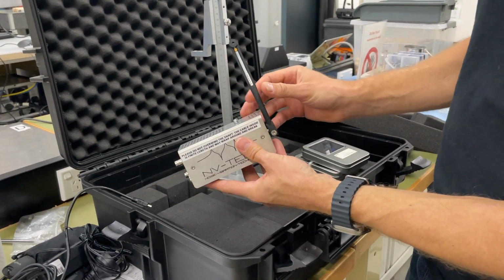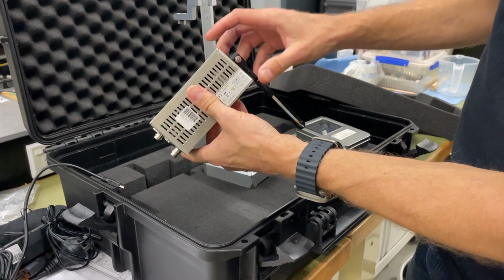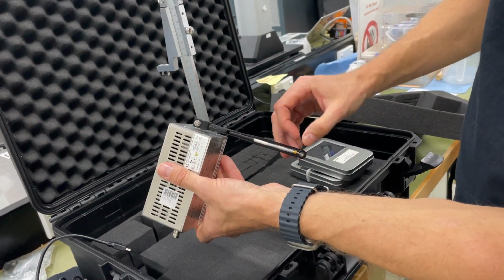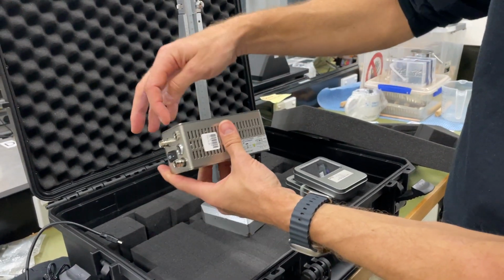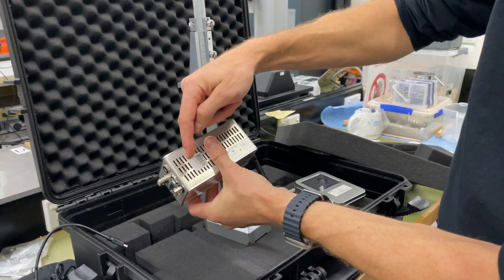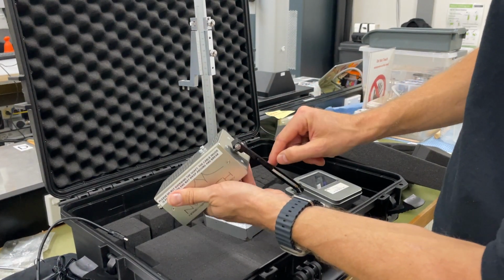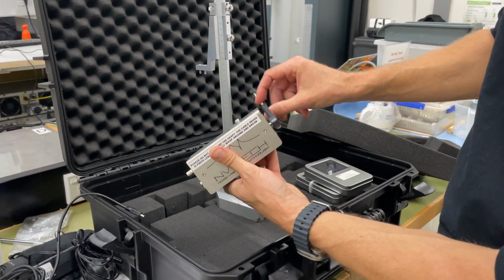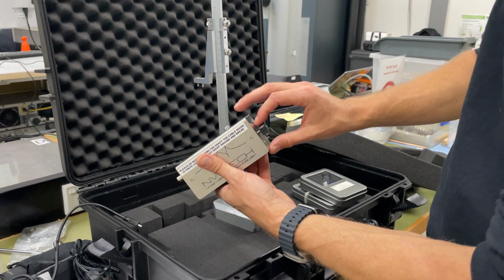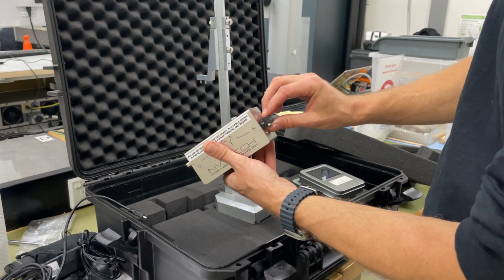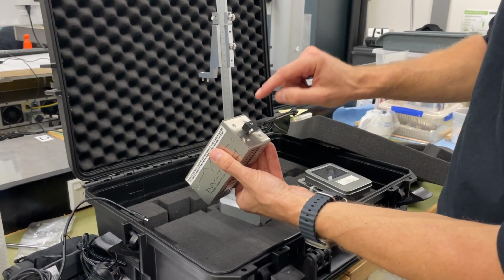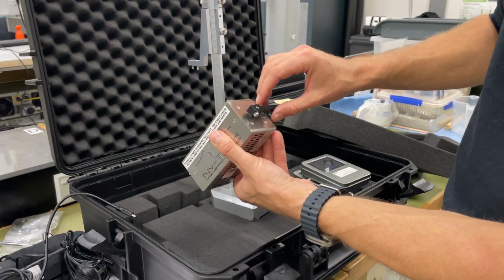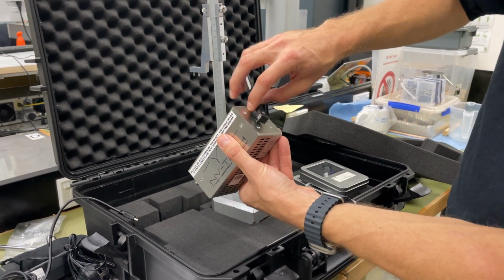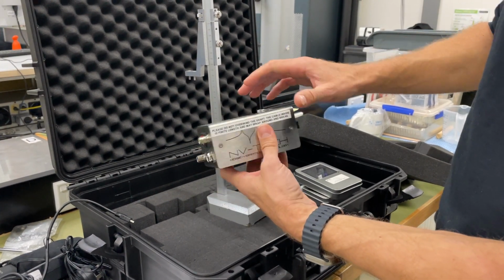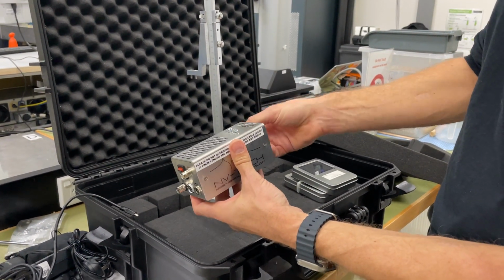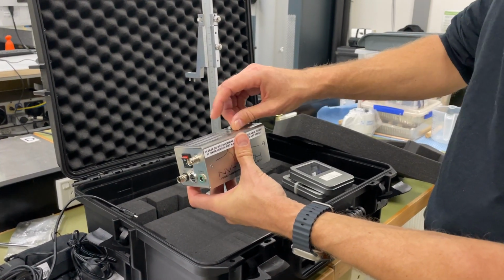One more thing to say about this hammer is that there is a cable connection inside of here between the force transducer, which constitutes the hammer, and the acquisition system. This cable is of finite length inside. It means that we can't continue to rotate and rotate the shaft many times, otherwise the cable will get wound up inside and will eventually fail, and we've done that previously twice. Soon we will be having a modification to this device sent from the manufacturer to prevent overwinding. It essentially will be a mechanical stop, but in the meantime please pay attention to these labels on the side asking you not to overturn or overwind the hammer shaft.